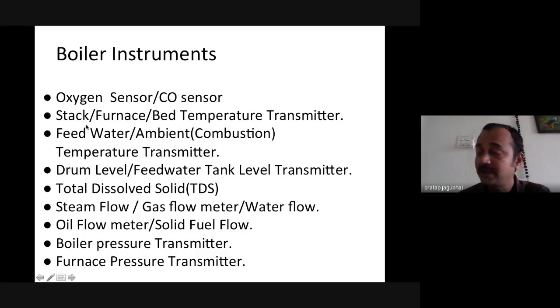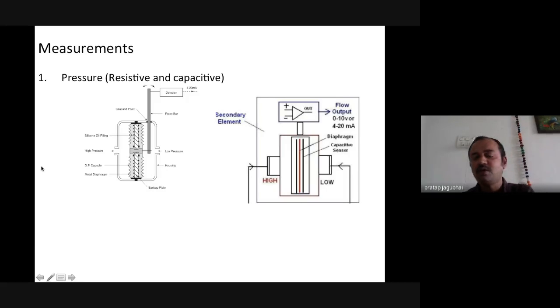Then flue gas temperature, furnace temperature, bed temperature, then feed water and combustion air temperature, boiler level and feed water tank level, dissolved solids to measure the silica, which is the inverse of the resistance, then the flow: steam flow, gas flow, water flow, fuel flow, and the pressure in terms of boiler pressure and the draft pressure. So now looking at this list of instruments, we can see that all these instruments can be made available using a physical parameter with the help of a transducer.